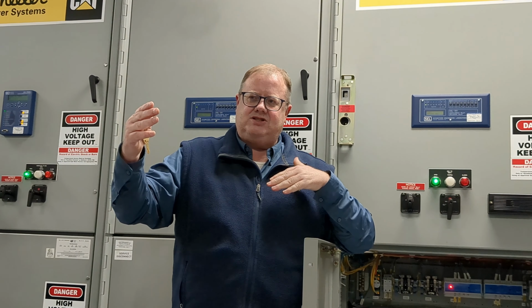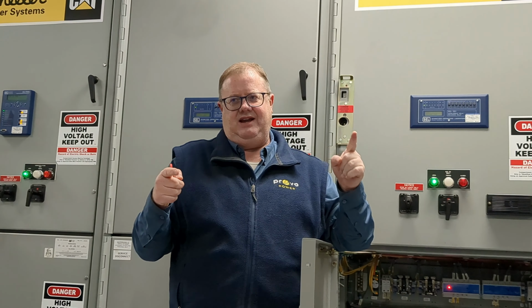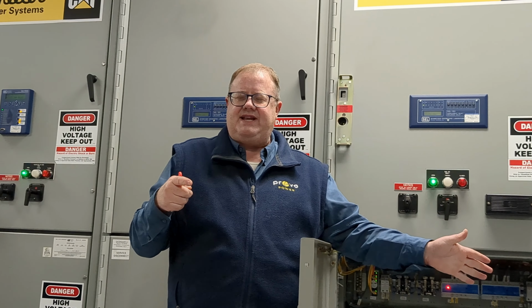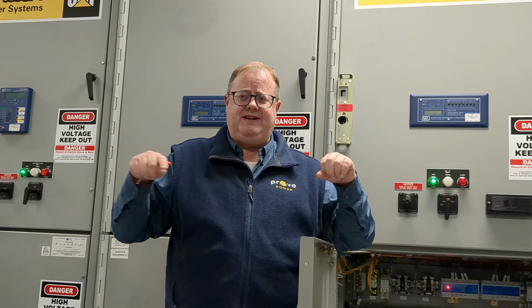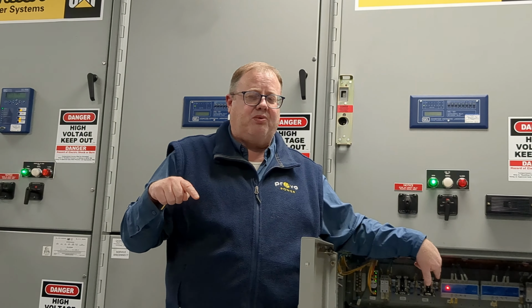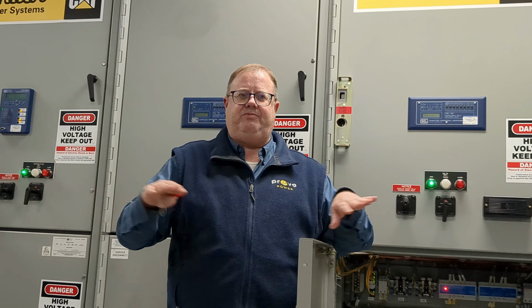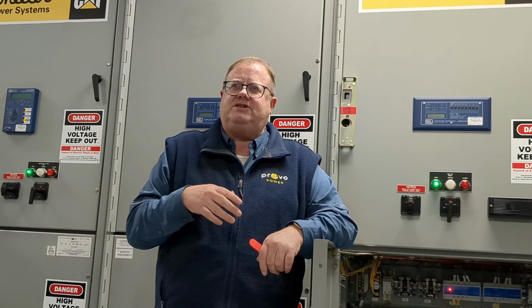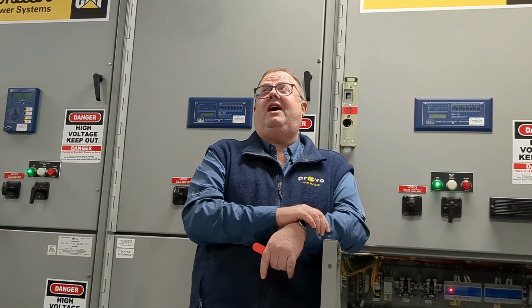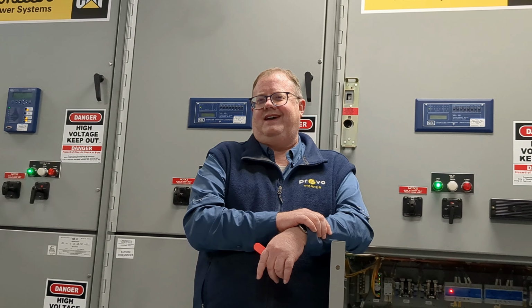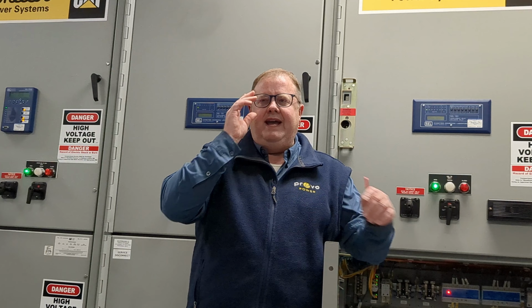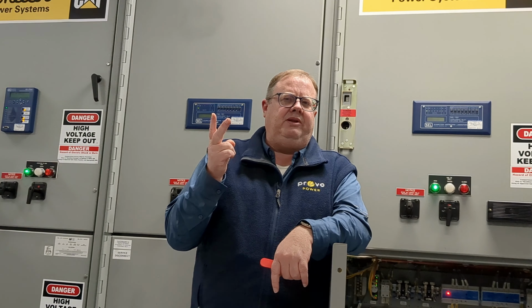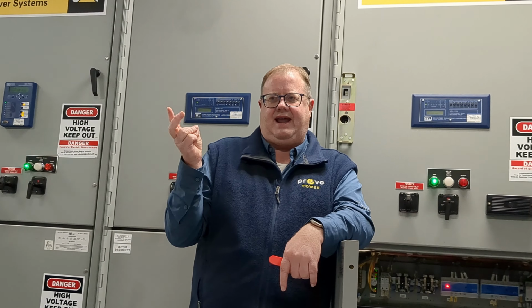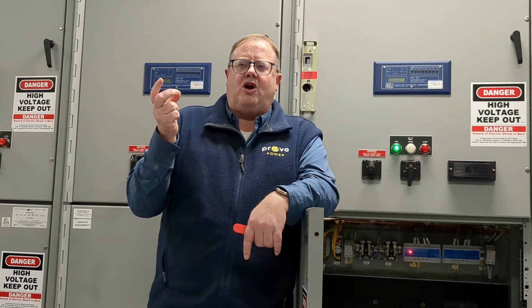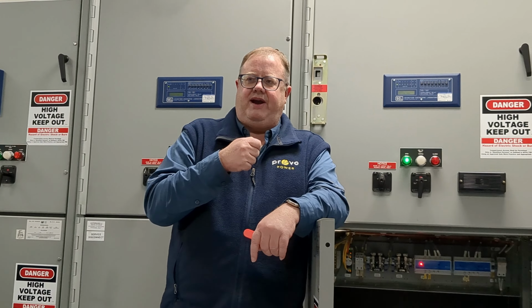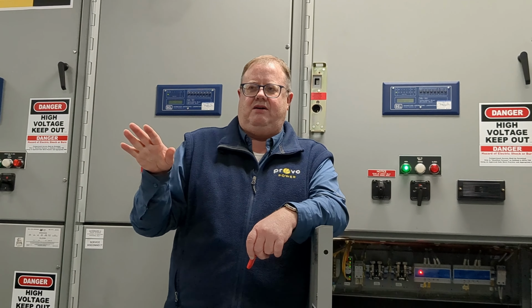So you design it. The first one we call the fuse saving scheme. We want the breaker to open up and then close down because most faults are temporary in nature. So you want just this breaker to open it up, clear the fault, close it, and everybody's back on power. So sometimes you see your lights go off, go on, go off, go on, go off, and they stay off, or they go off and then they come back on. It's just the breaker operating. So we normally close it 2 times and then the 3rd time we lock it out because it's a permanent fault. What we're hoping to do is that we open the breaker, the fault goes away. We close it, everybody's back on power.